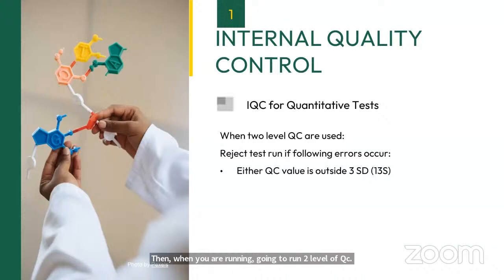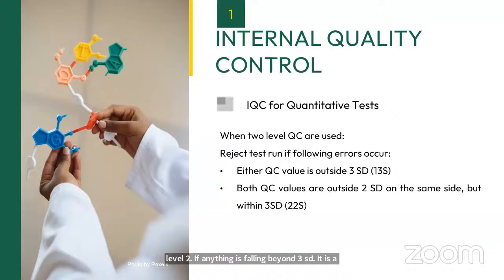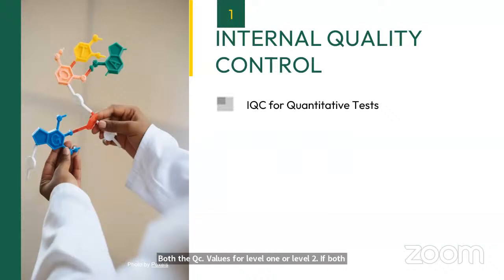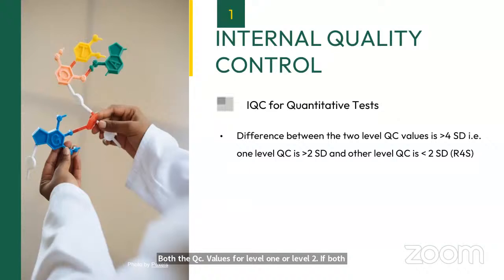Either of the QC values outside 3SD. So even if you are running two levels, any QC value for level 1 or level 2, if anything is falling beyond 3SD, it is a rejection. If both the QC values, level 1 and level 2, are falling beyond 2SD, again it is a rejection. Then differences between the two QC levels: if level 1 QC is plus 2SD and level 2 is minus 2.3SD, the difference between the two levels is more than 4SD, so again it is a rejection.